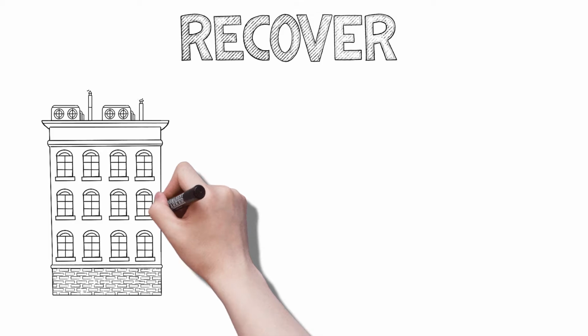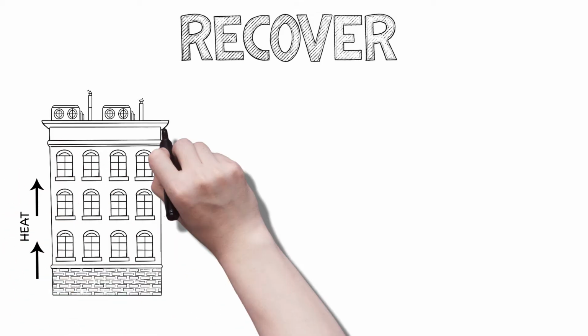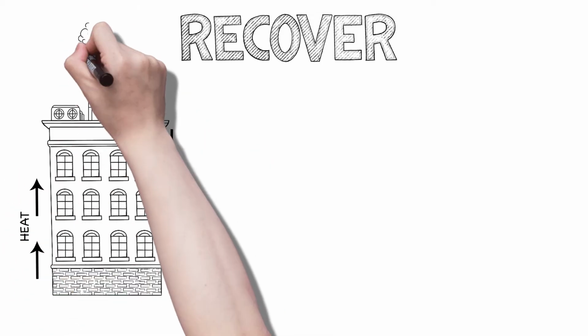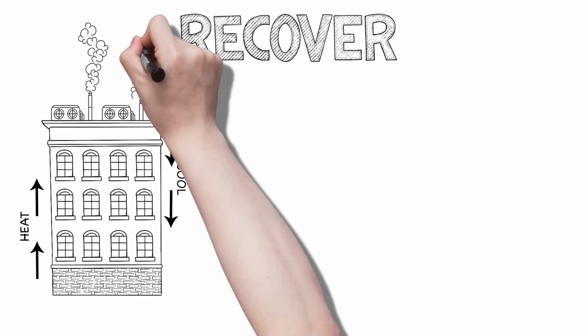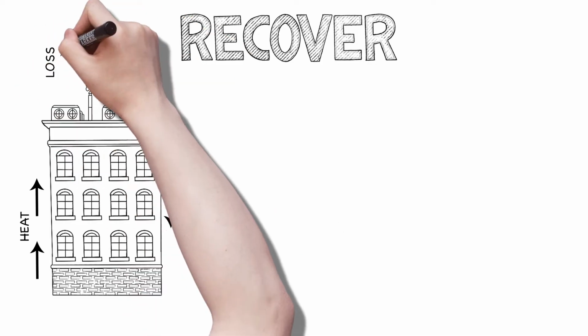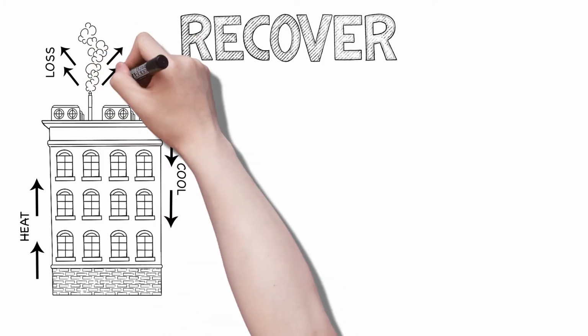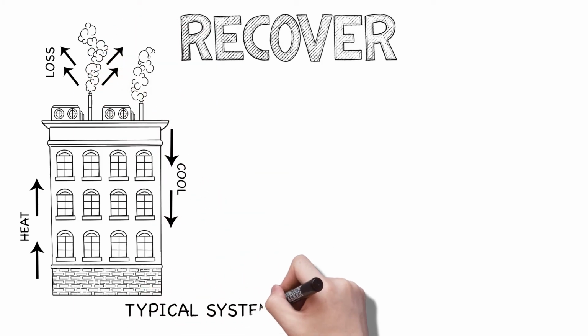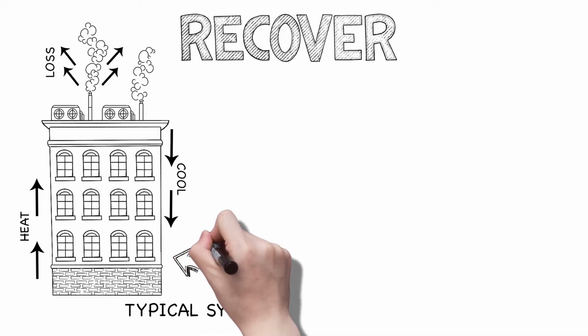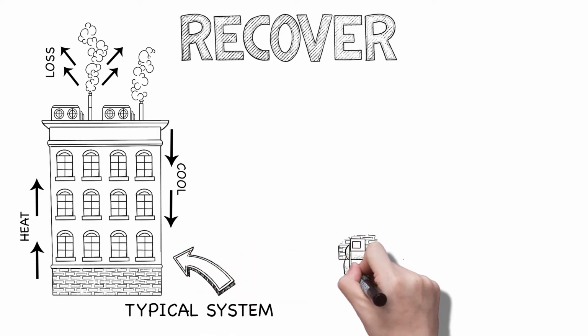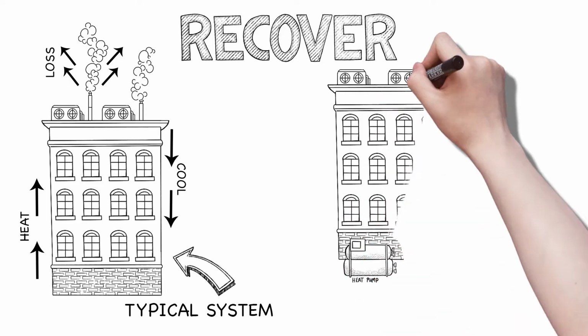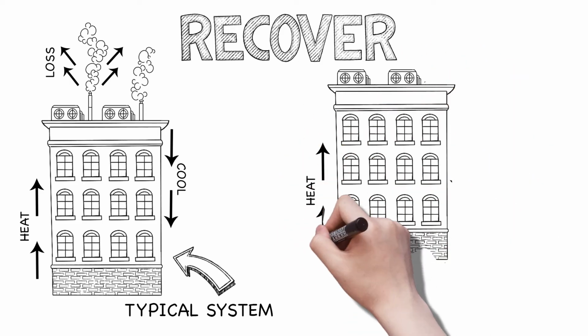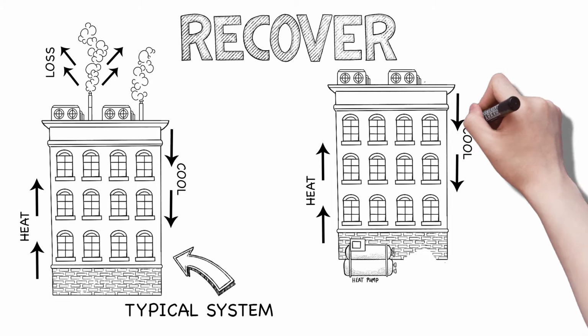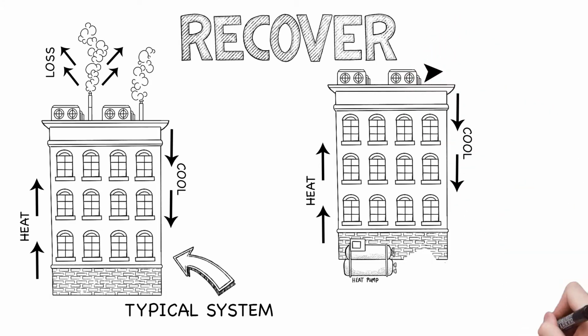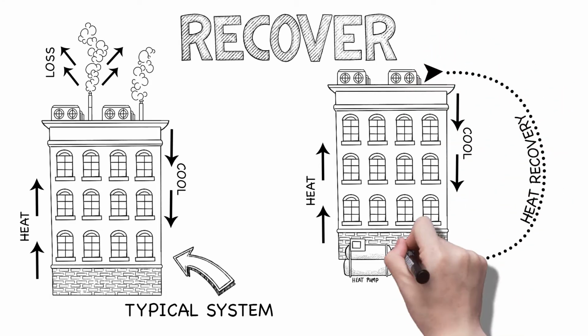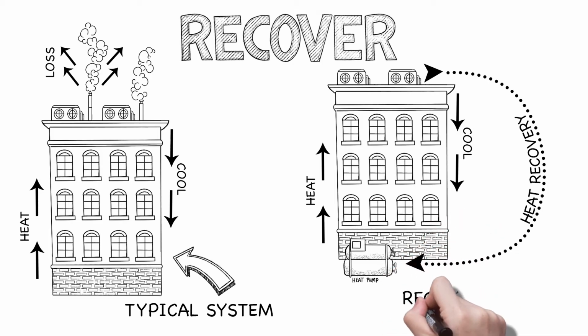Heat pumps are a great tool to accomplish this. Heat pumps transfer energy between cooling and heating load centers. Think about summer reheats used for dehumidification, or process cooling loads in the winter. Heat pumps can transfer energy between these simultaneous heating and cooling loads, reducing overall energy usage. To say it another way, rather than operating a cooling tower and a boiler at the same time, let's take the energy being rejected off the cooling tower and put it back in the building to use it.